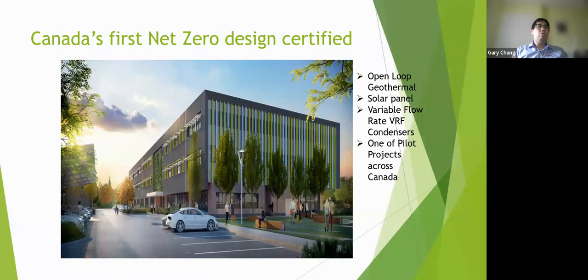Besides that, there's also a case, the Canada First Net Zero Design Certified building, in Waterloo. This is the first office building utilizing a net zero design: open loop geothermal, solar panels, variable flow VRF condenser as the water source condenser. Using geothermal means using ground heat - during summertime you reject all the heat from the building, and in wintertime you absorb the heat you rejected during summer to help maintain comfort in the building space.